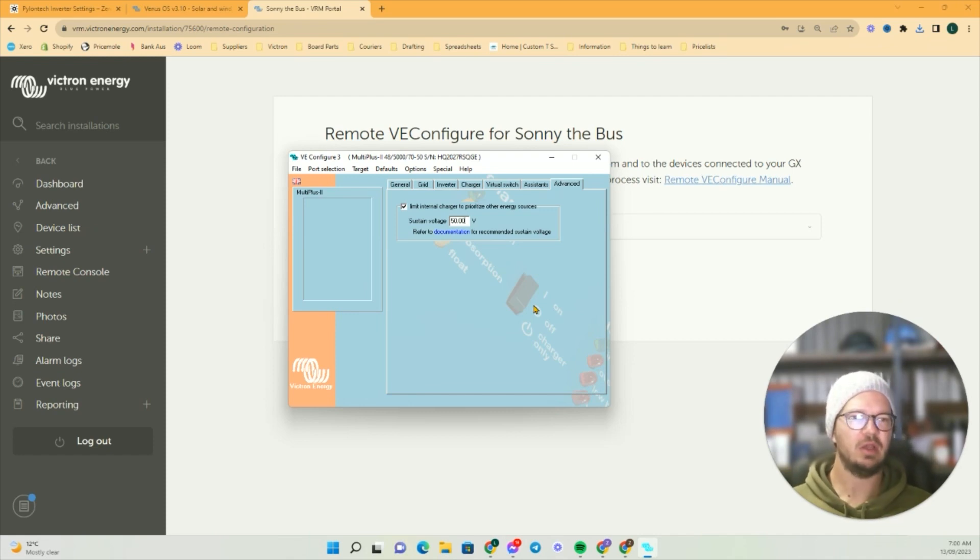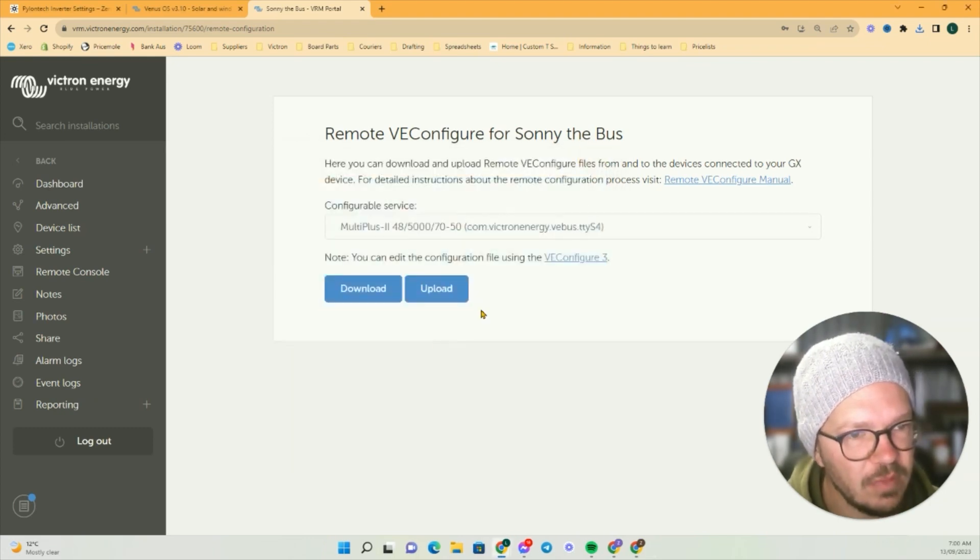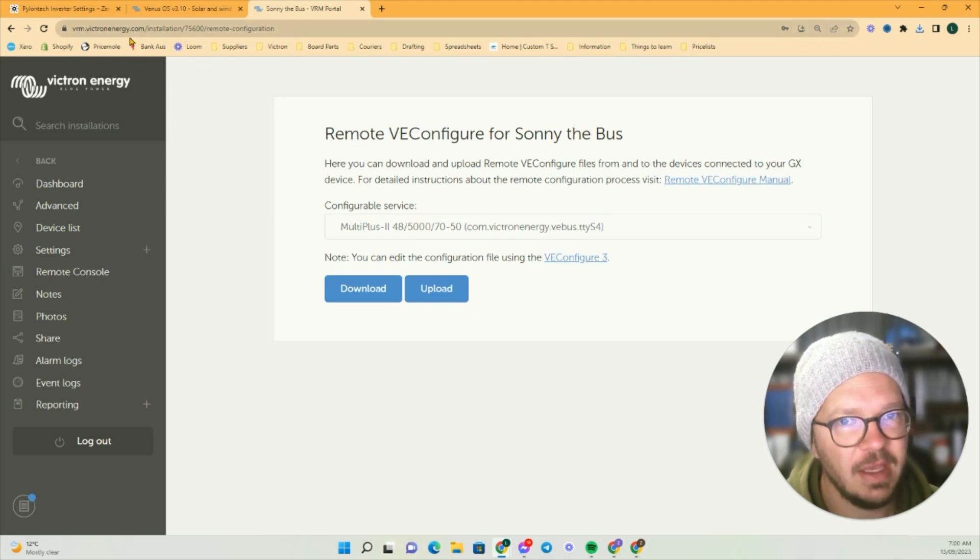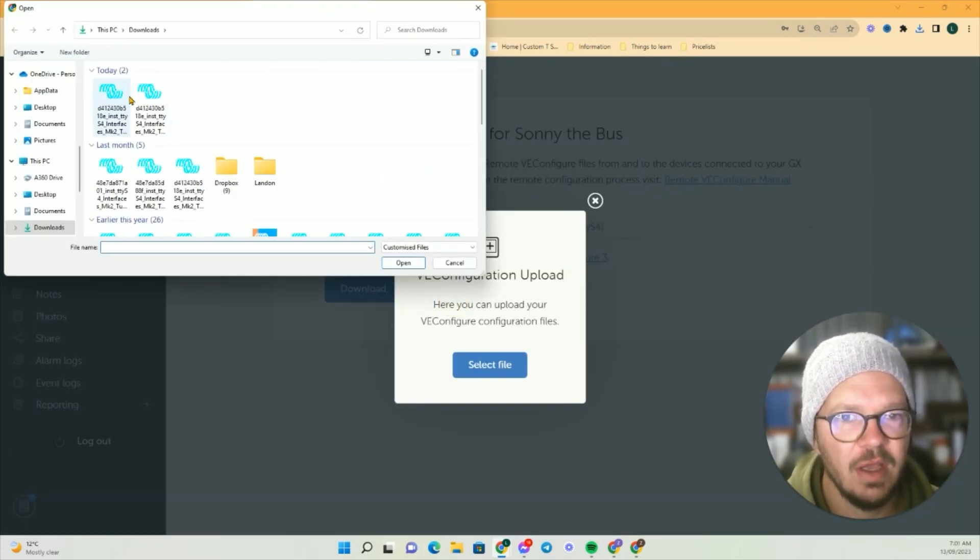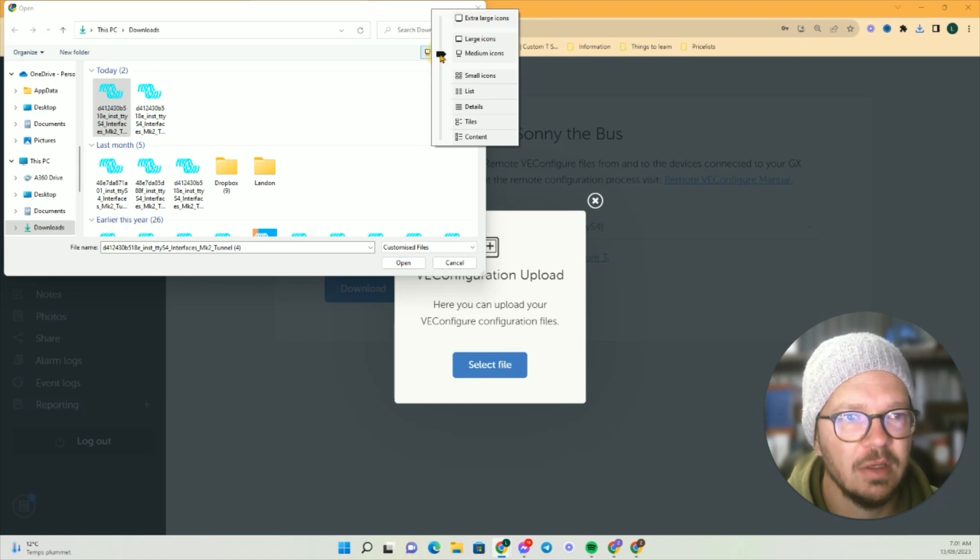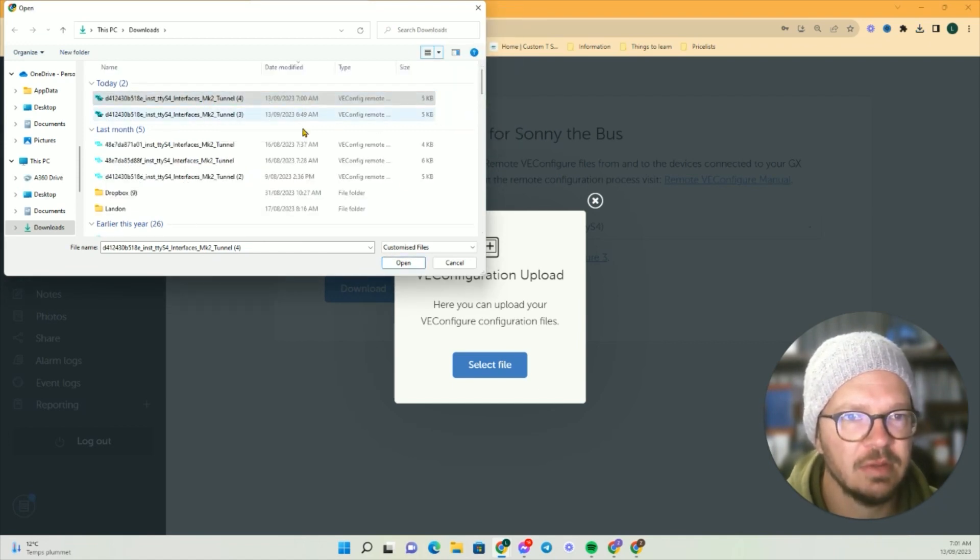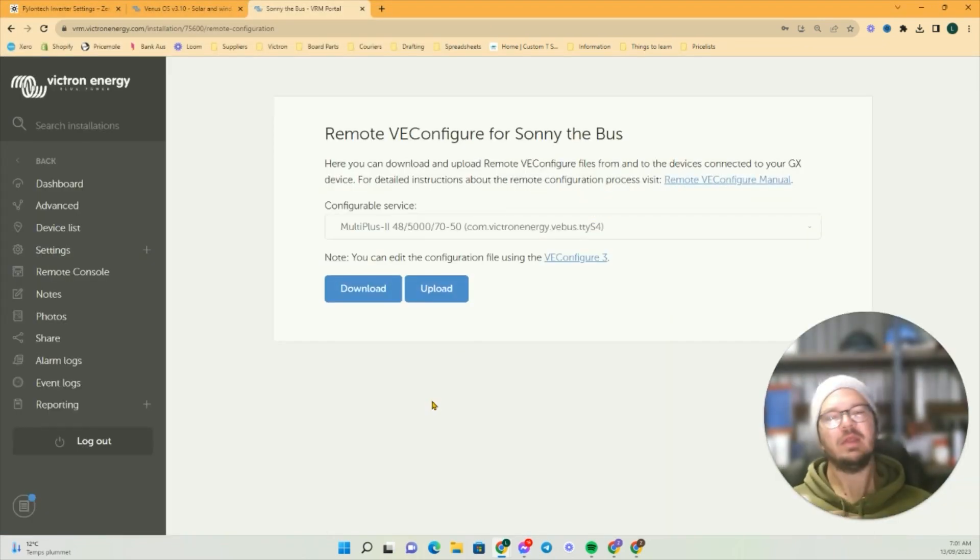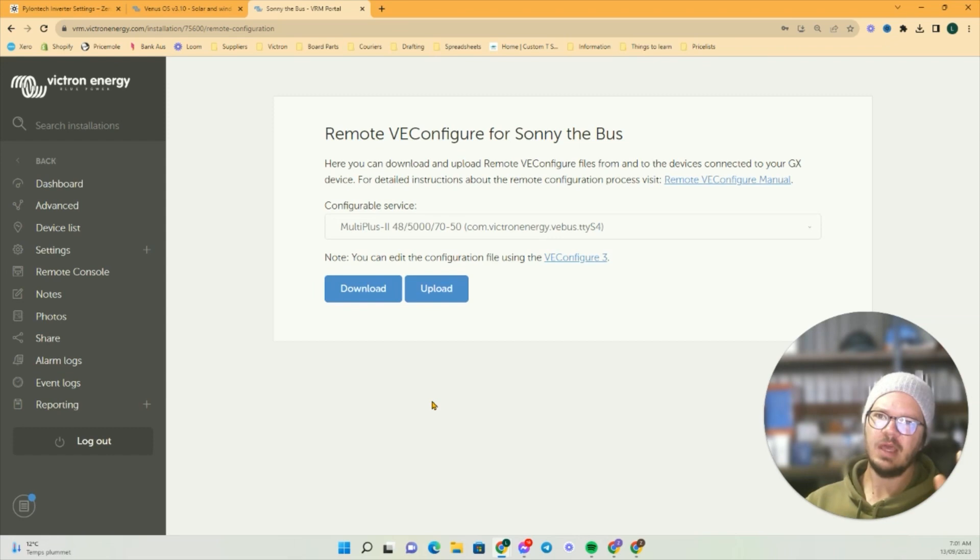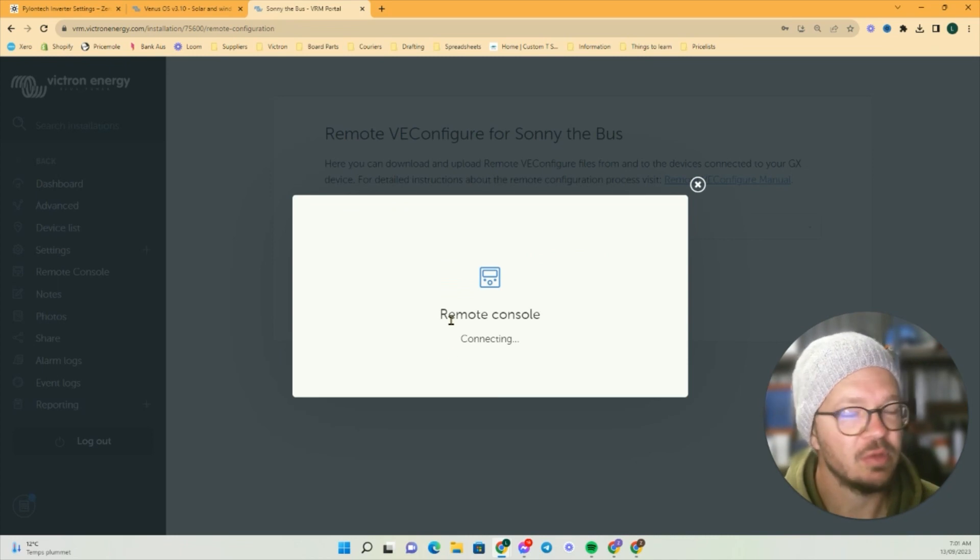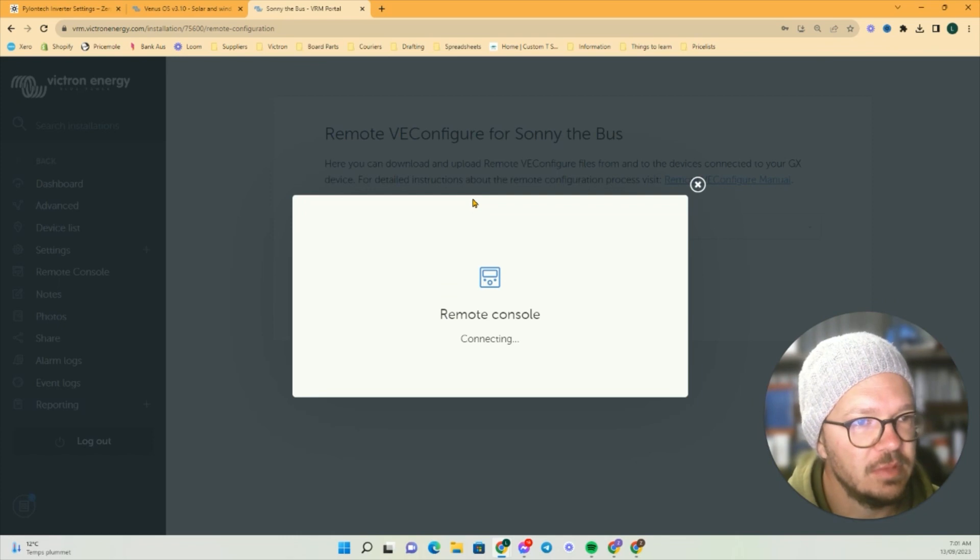We tick this box, add in that value, we go Escape—usually it has an option to Save. Then back here on the VRM we go Upload, Select File, and it'll be the newest one. This one here, 7am, is the one that we want. Then we go Open, and that'll upload. Often during the upload process, the inverters will power off and then power back on, which is all normal. Sometimes the relays go clickety-clunkety as well, which is all good.